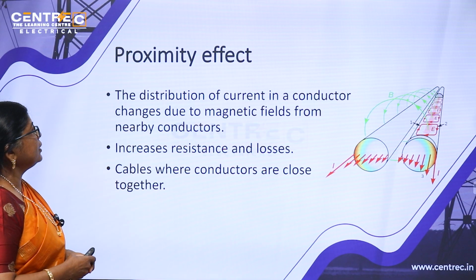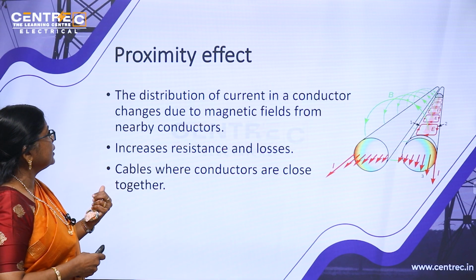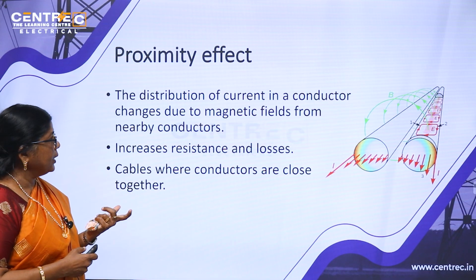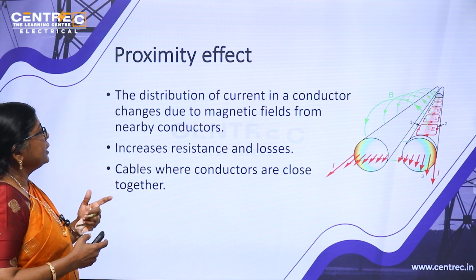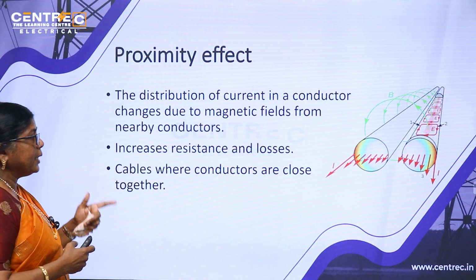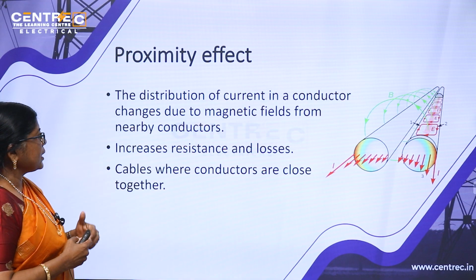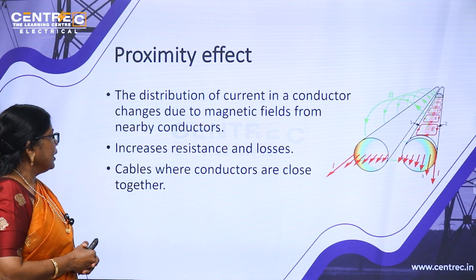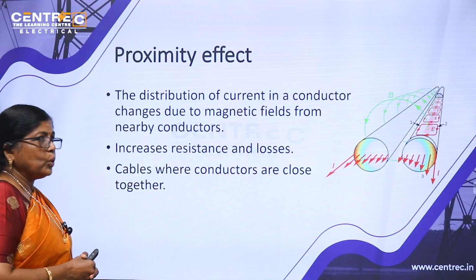Proximity effect: the distribution of current in a conductor changes due to magnetic fields, that is also an inductive effect, from nearby conductors. So it increases resistance and losses in cables where conductors are close together.